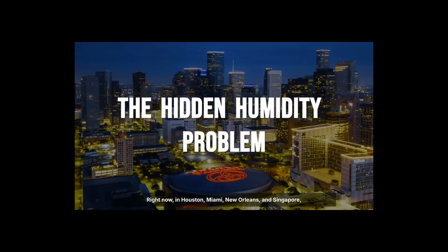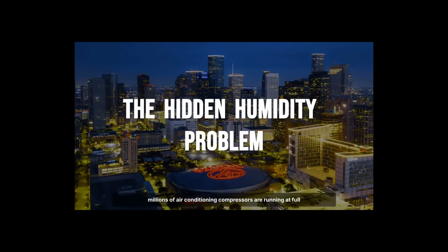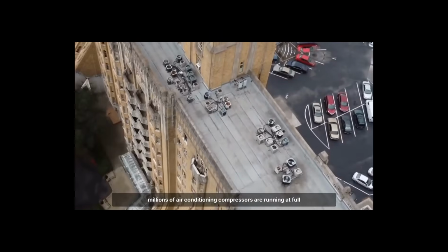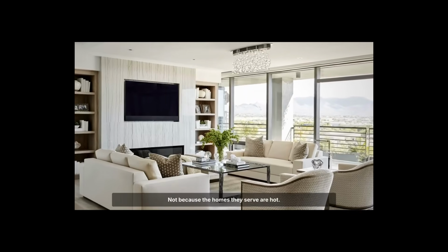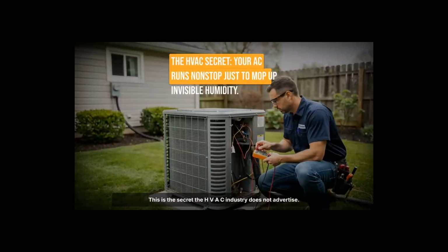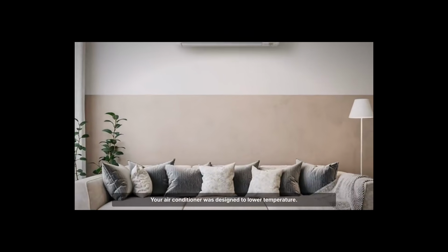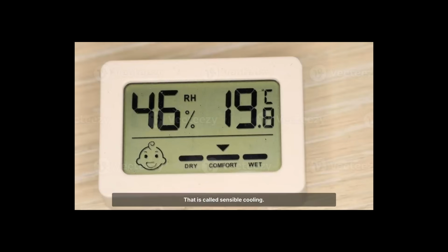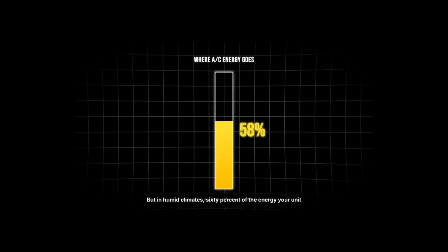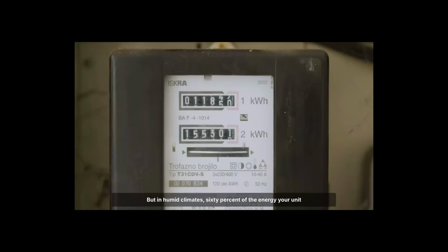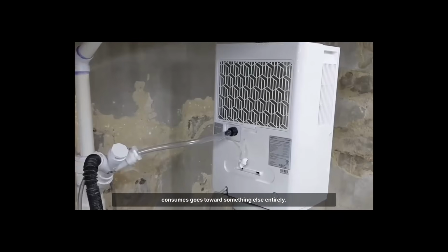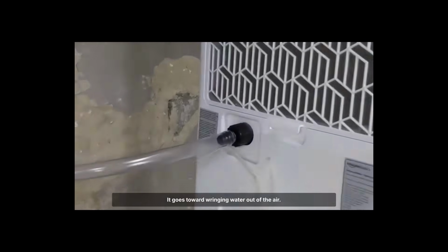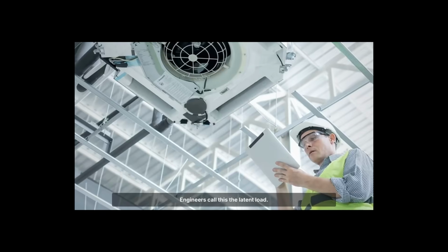Right now in Houston, Miami, New Orleans, and Singapore, millions of air conditioning compressors are running at full capacity. Not because the homes they serve are hot, because the homes they serve are wet. This is the secret the HVAC industry does not advertise. Your air conditioner was designed to lower temperature. That is called sensible cooling. But in humid climates, 60% of the energy your unit consumes goes towards something else entirely. It goes toward wringing water out of the air. Engineers call this the latent load.